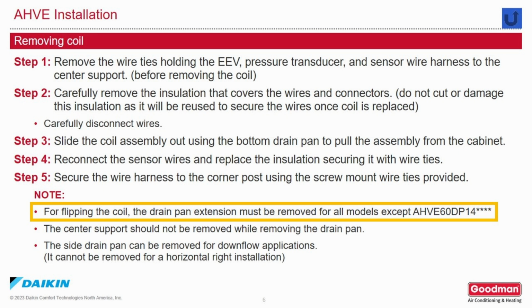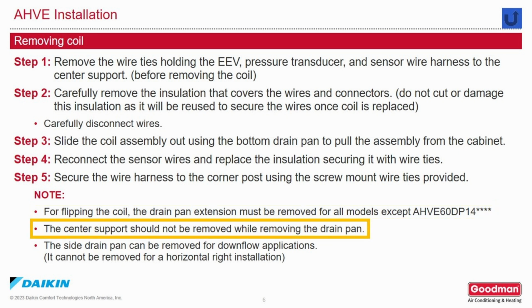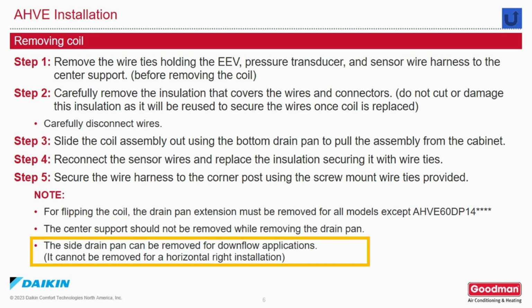Please note, for flipping the coil, the drain pan extension must be removed for all models except for the AHVE 60 DP14. The center support should not be removed while removing the drain pan. The side drain pan can be removed for downflow applications. It cannot be removed for horizontal right installation.